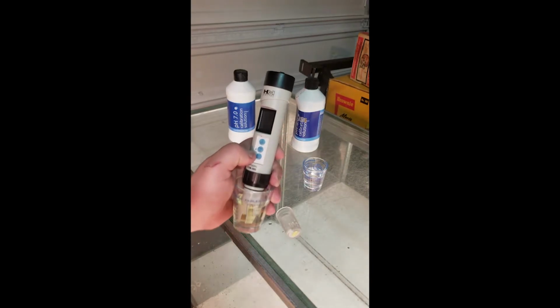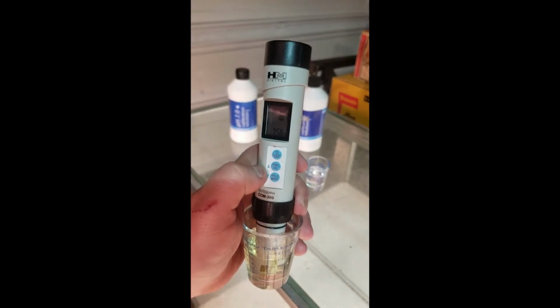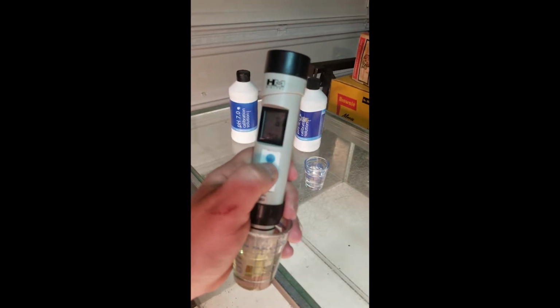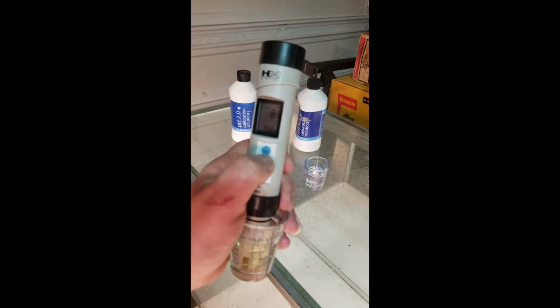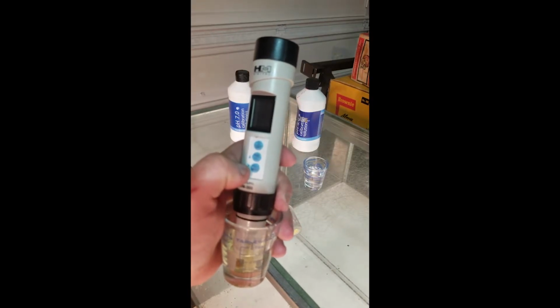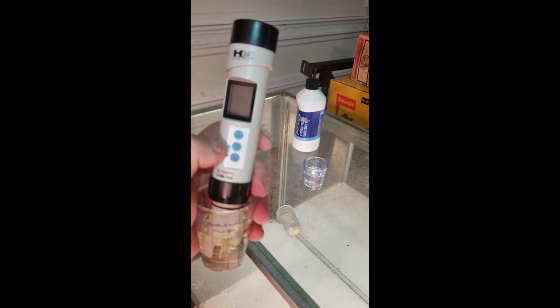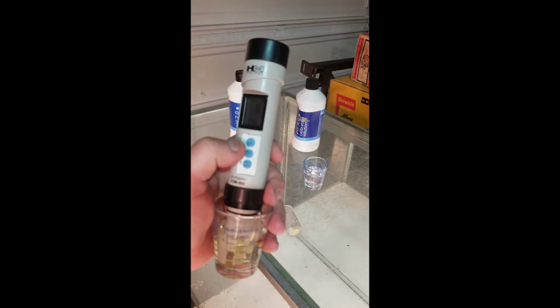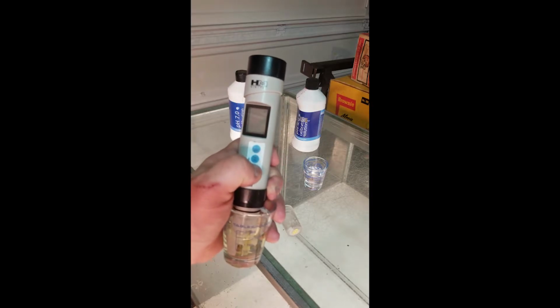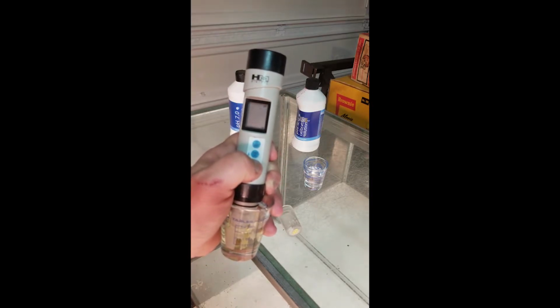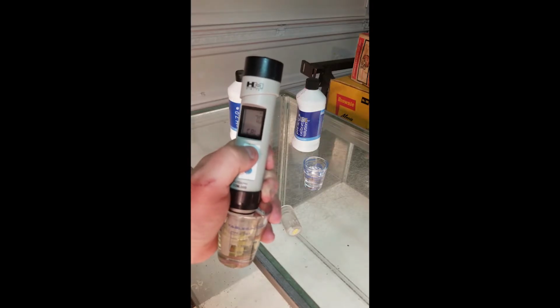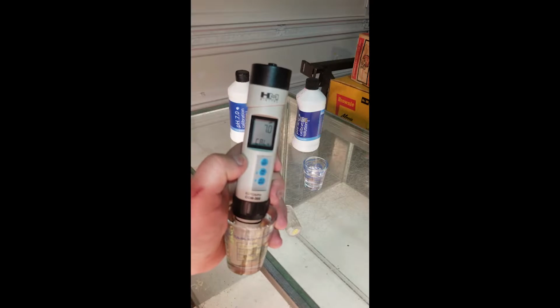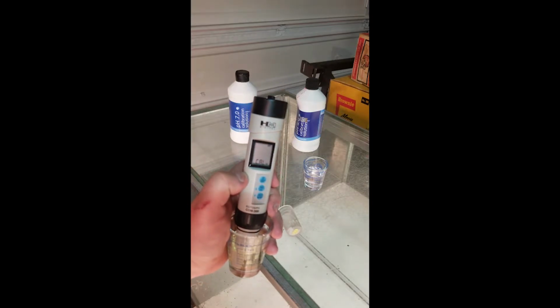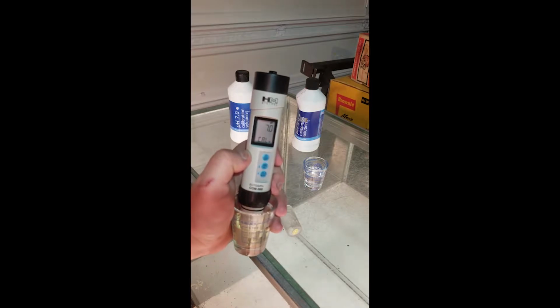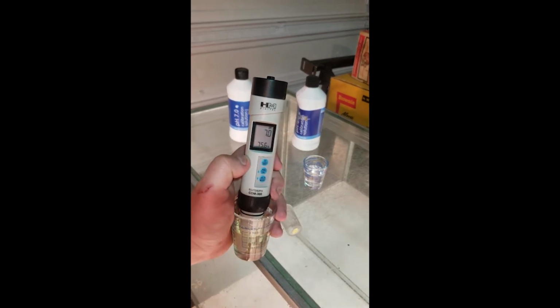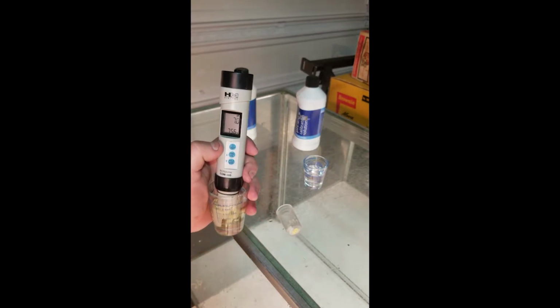So on this meter, I'm going to press and hold the calibration button, which is in the center. This is HM Digital's handheld trimeter. It's temperature and TDS, but you have to switch between the TDS and pH. And then with the up and down arrows, while in the solution still, I'm going to bring it all the way down to pH of 7. And I'm just going to hit enter once, and it's going to flash cal, and that should calibrate. And then when that is done, it'll stop flashing and it'll say end.